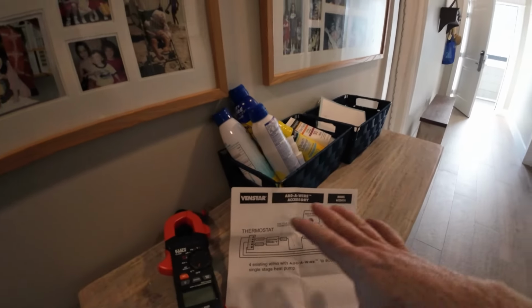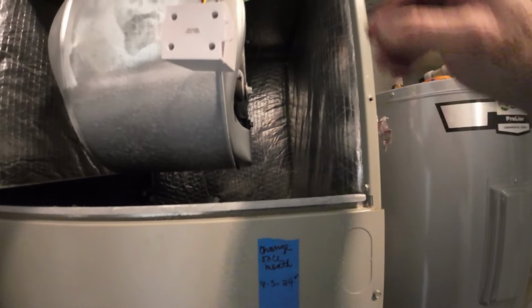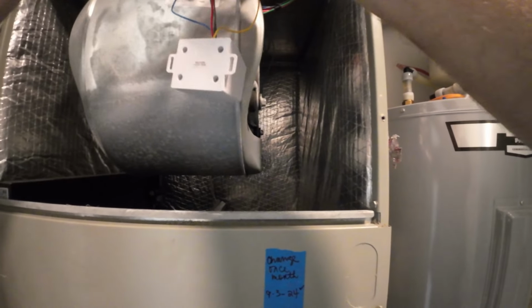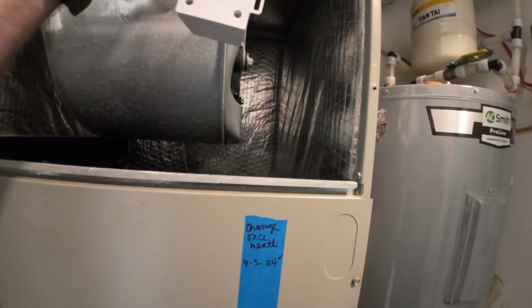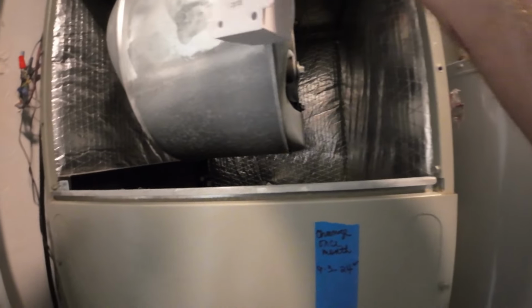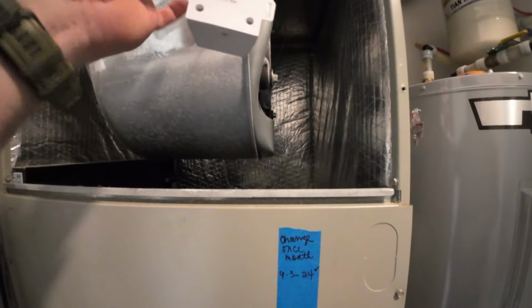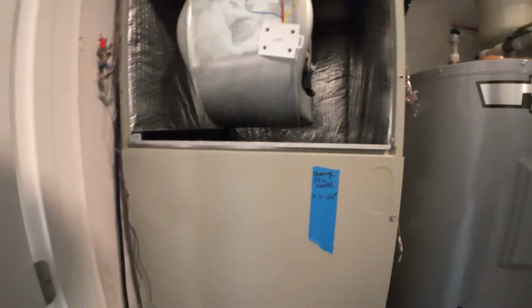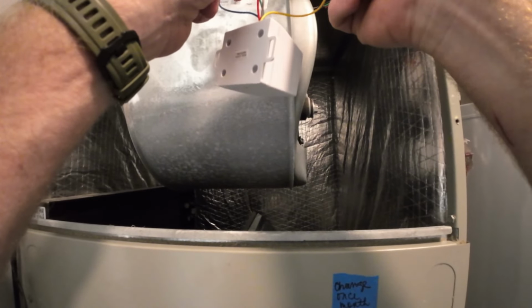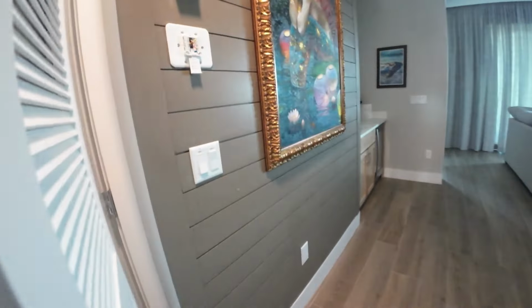Okay, so I just got done figuring this out, wiring it up. And initially what I did is I kept the red going all the way to the thermostat, blue the blue, white the white. These it didn't matter because this is a condenser. I pretty much just got rid of the yellow call. And then what happened is yellow and green. I used the green wire for the communication blue wire because we're going to use the green for the fan on that little diode. So the diode makes this wire turn into these two wires, theoretically. So I used the green wire, ran it over. I have the green and the yellow here tied into that green wire for communication.